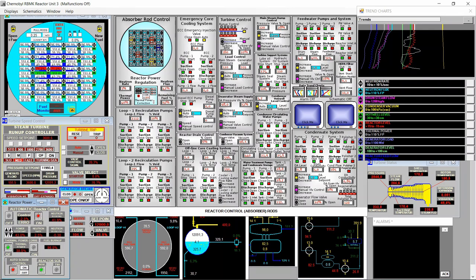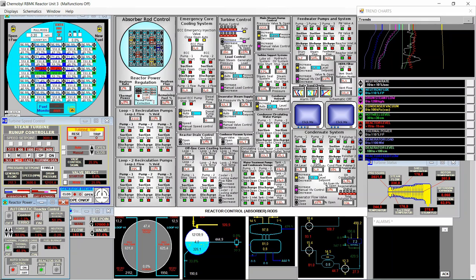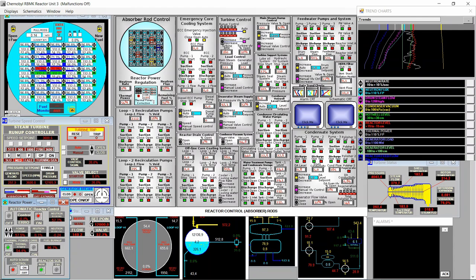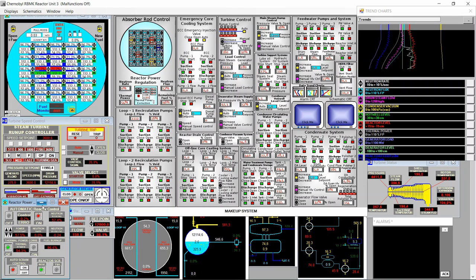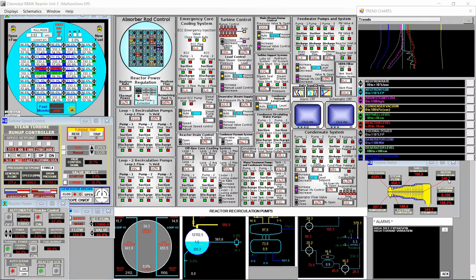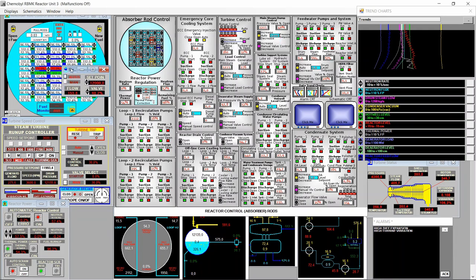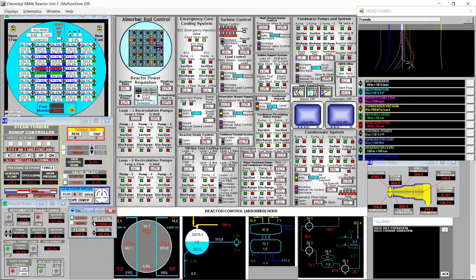The turbine is heading to auto — this means it keeps the pressure it had at the moment we synchronized to the grid, which is 11,993, and it keeps the valve control opening at the value that maintains this pressure. I increase the power set point to 200 percent, but I need to be careful because the differential expansion is increasing a lot — there are about 40 degrees difference between the shell and the rotor. I'll set the main steam dump control to the maximum at 13,500.